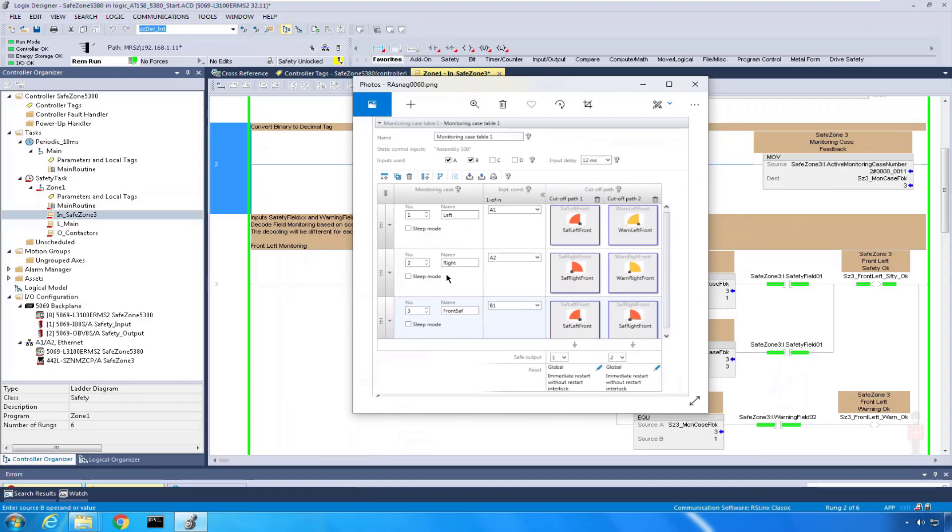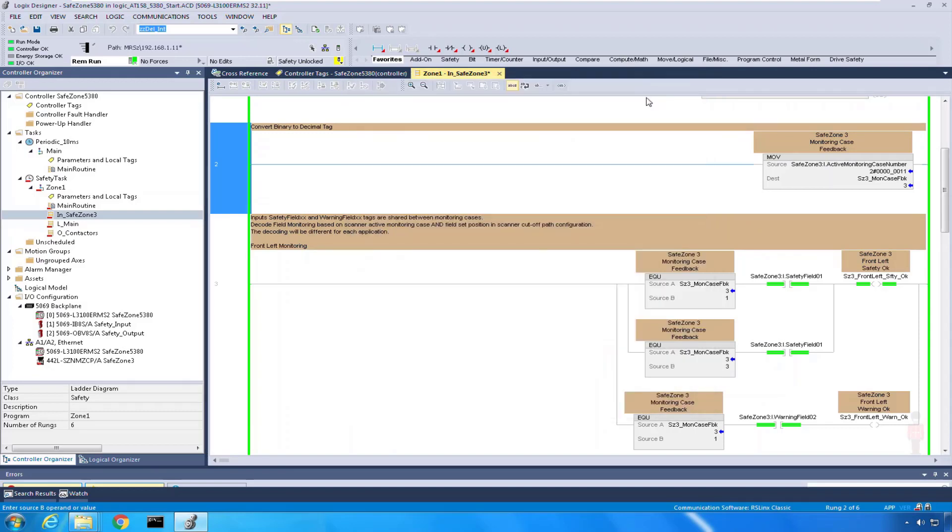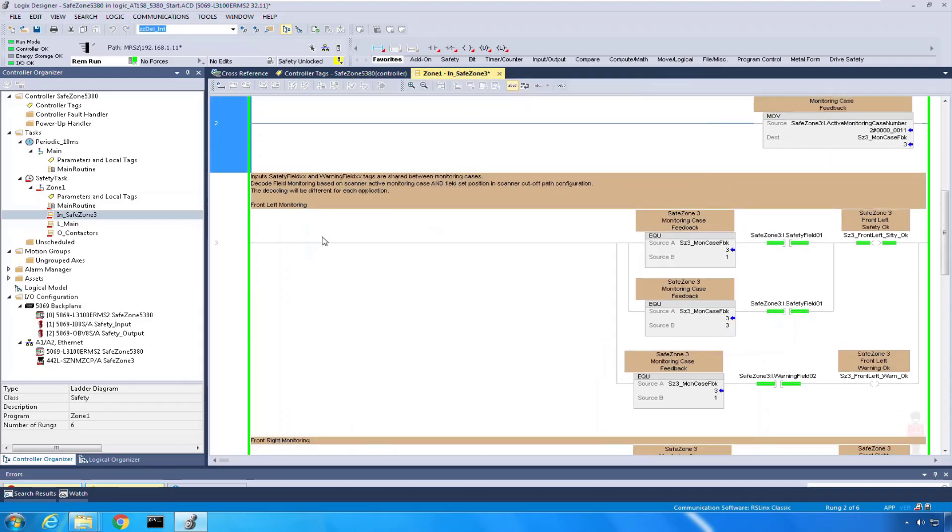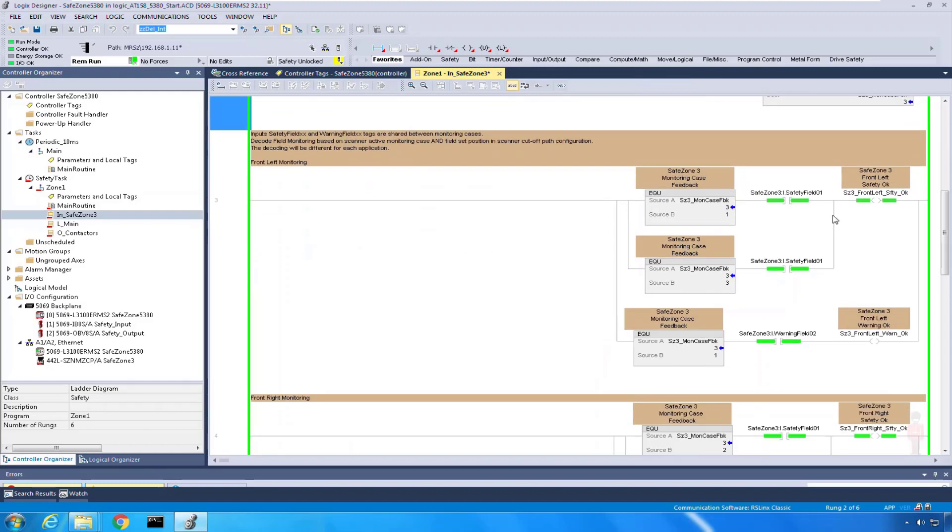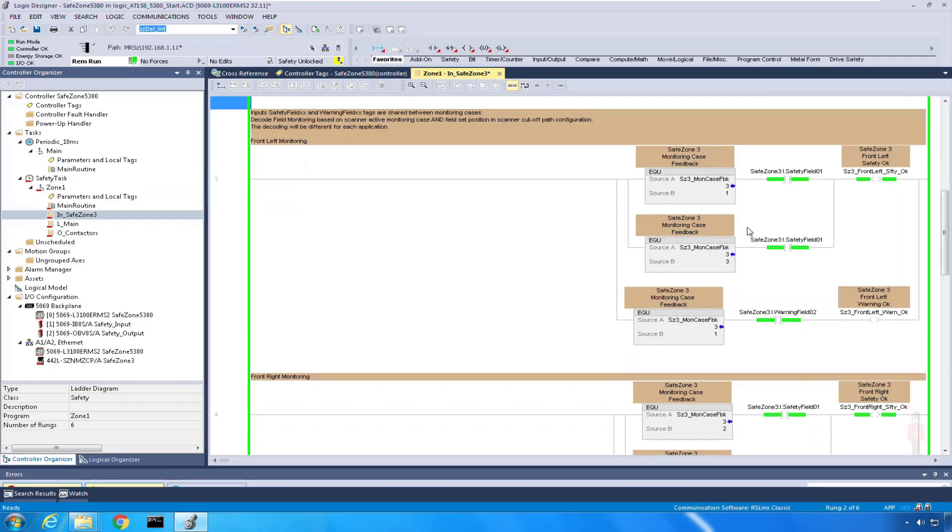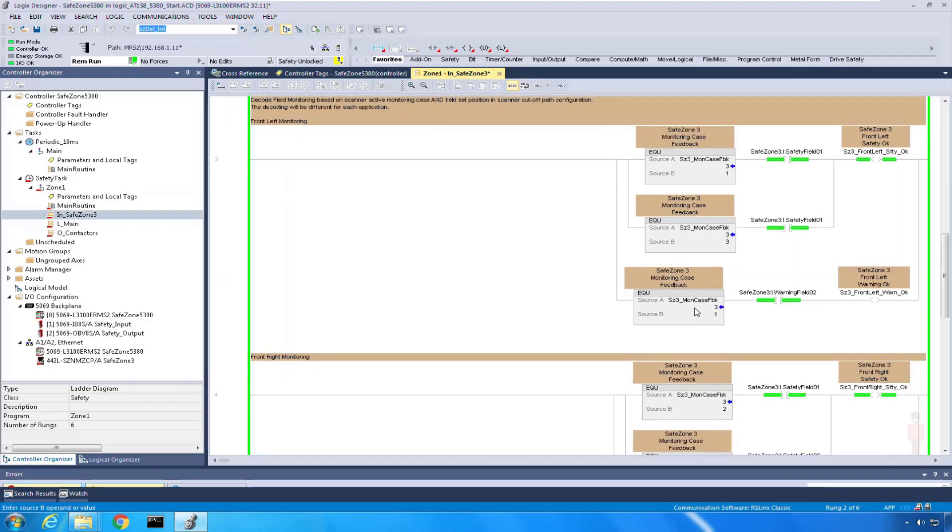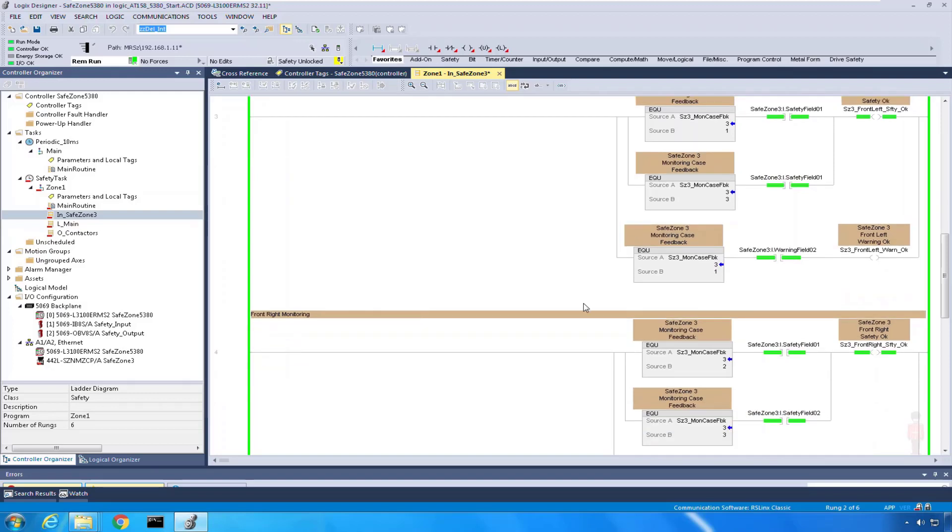If you recall, for each of the different monitoring cases, I'm going to get a different input based on the safety. It's output from the scanner, input to the device. So I need to decode that in my monitoring cases. For left safety to be okay, it's got to be monitoring case 1 and 3, and that safety field 0 and 1. I just kept that logic the same so I can repeat it quite quickly. Also, in monitoring case 1, if I get a field warning, that's going to say my left warning field is okay.